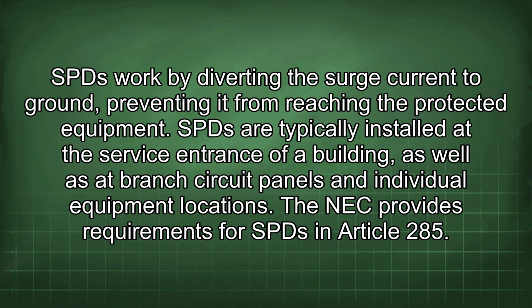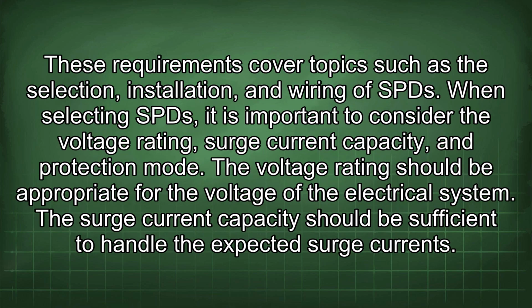SPDs are typically installed at the service entrance of a building, as well as at branch circuit panels and individual equipment locations. The NEC provides requirements for SPDs in Article 285. These requirements cover topics such as the selection, installation, and wiring of SPDs. When selecting SPDs, it is important to consider the voltage rating, surge current capacity, and protection mode.